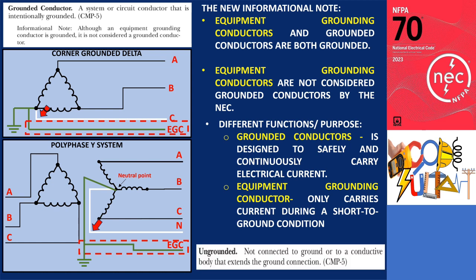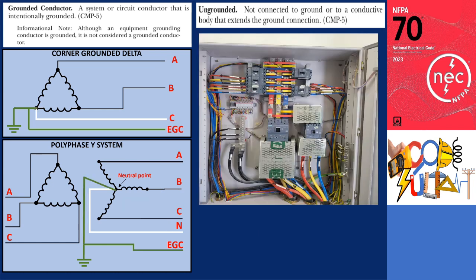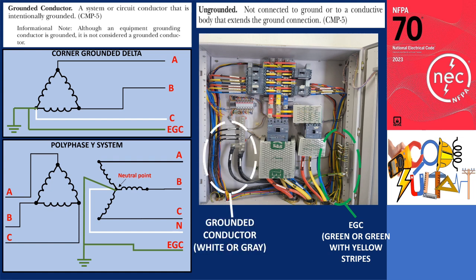In Article 100, an ungrounded conductor is defined as not connected to the ground or to a conductive body that extends the ground connection. Therefore, in the delta corner ground system, phases A and B are the ungrounded conductors. In the polyphase Y system, phases A, B, and C are considered ungrounded conductors. It is important to note that the neutral conductor is not always a grounded conductor unless the neutral point is grounded. In a typical panel board installation, specific color coding is required: the equipment grounding conductor must be green or green with yellow stripes, the grounded conductor should be white or gray, and the ungrounded conductor should be distinguished by colors other than white, natural gray, or green — alternatively, a combination of color plus distinguishing marking can be used.